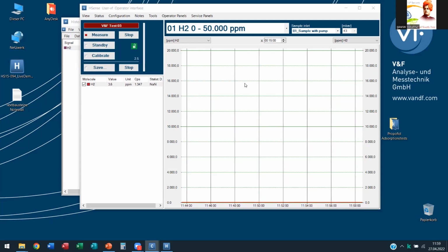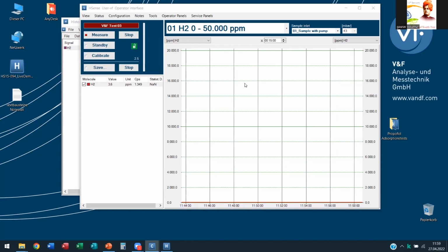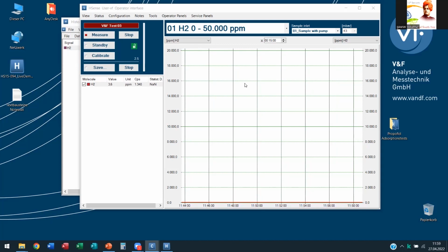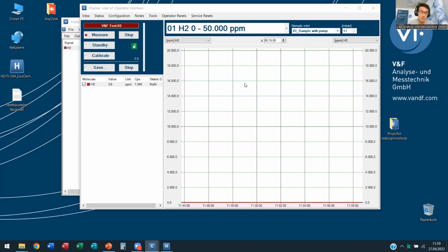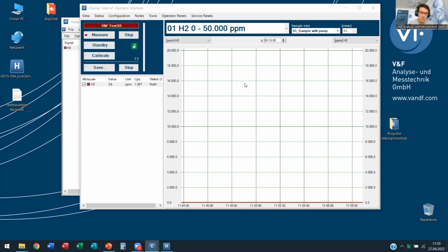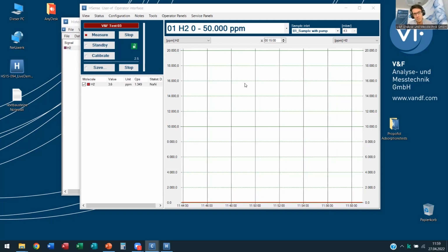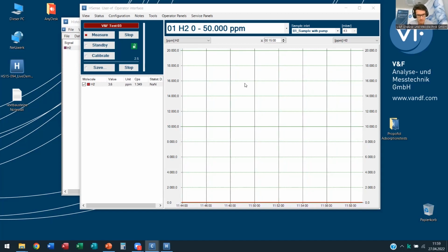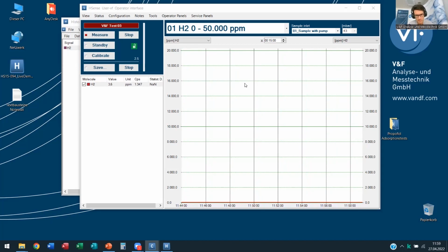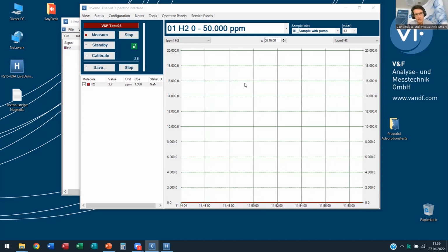I mean to say that the filters, whatever are there in the line, are sufficient to clean up the system as of now. Yes, of course. That's why they are there. All the particulates will be trapped in this filter, so that the dirt does not get into the downstream gas inlet system. So the vacuum chamber needs to be clean, and also the interior piping is usually always clean.